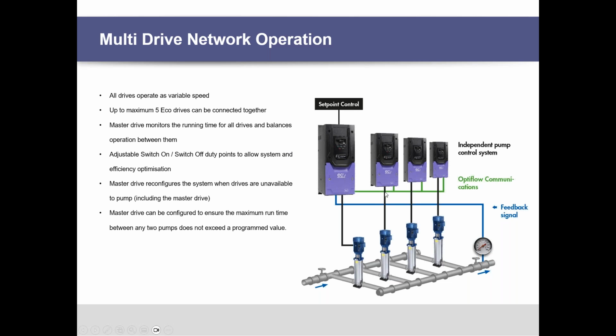And in the configuration that we have with OptiFlow, that's our own proprietary control algorithm for booster pump sets. If one of these motors is taken offline, say for maintenance or something like that, then another one will automatically take over. You can even turn off the main power to the master drive, the main drive, and another one will automatically just take over. So there's a huge amount of redundancy built in here to give your customers peace of mind.